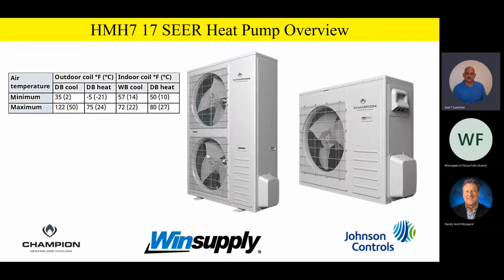The other thing we always like to point out right away is that the unit, even though it kind of looks like a mini split, is not a mini split product. Let me say that one more time. This is not a mini split. It kind of looks like it. It has some similar compressor technology as far as inverter drive. It'll modulate from 35 to 100% capacity. But I want you to think about it as just a heat pump. It's just another heat pump.